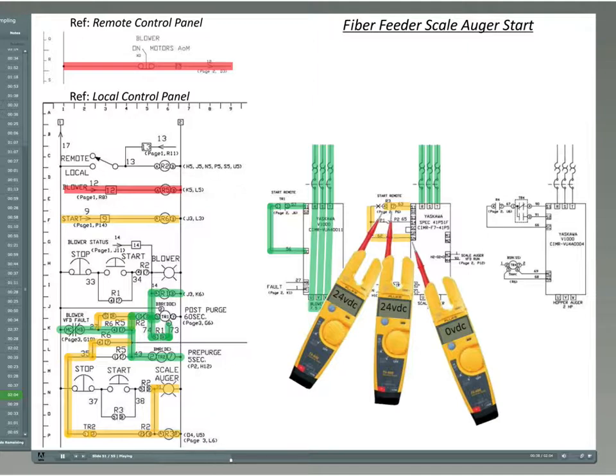During the time delay period, an auger motor start signal comes in on terminal 6, which enables R6. A normally open contact of R6 closes, which is intended to start the scale auger motor. The scale auger motor does not start since TR2 has not timed out yet, and its normally open contact is still open. When TR2 times out, its normally open contact closes. Due to a bad connection, the scale auger does not start.